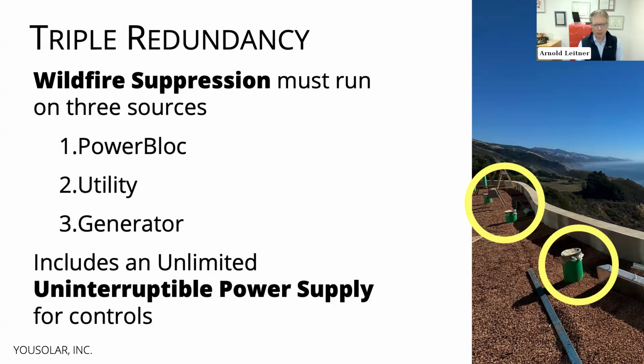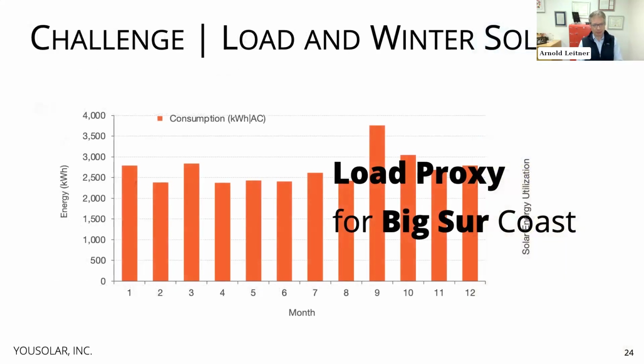But remember, in all of this there also has to be an uninterruptible power supply for the controls, and that needs to run for days, while its UPS only lasts for hours. So we backed up that UPS with switching so that any of those three sources will always provide power to it, which in turn keeps the controls completely uninterrupted. That was the single line diagram I showed you earlier.